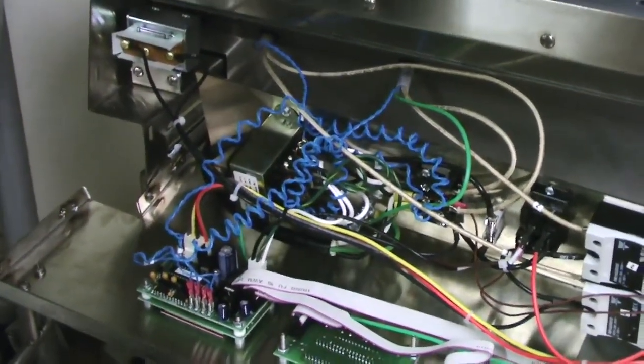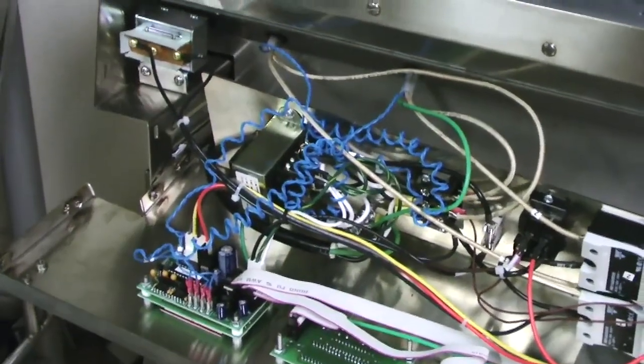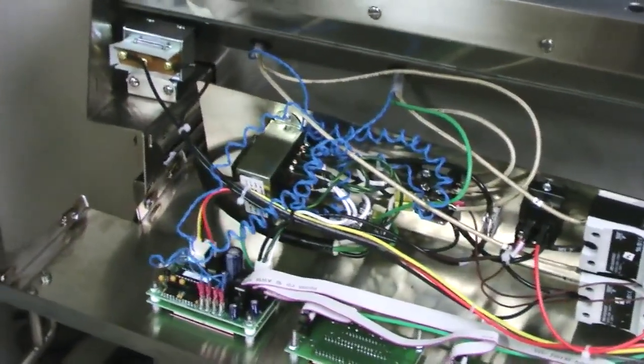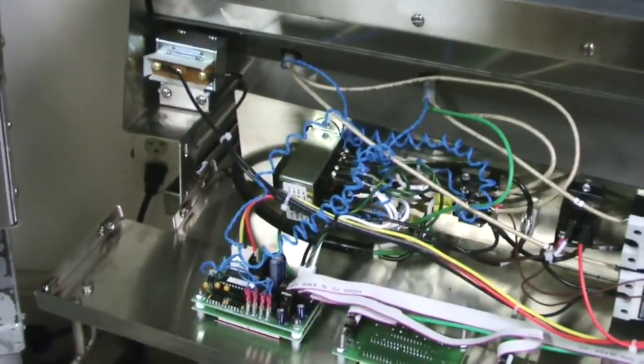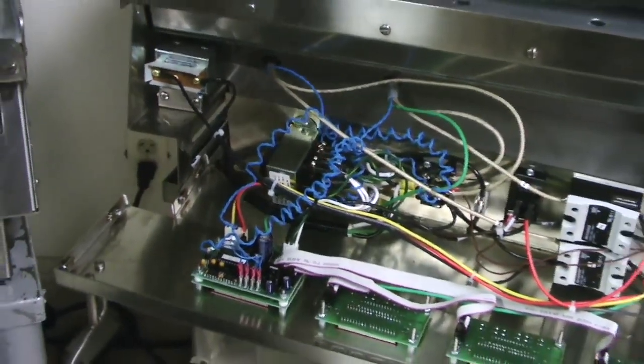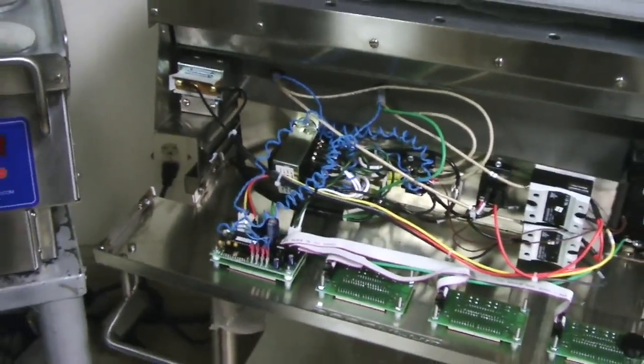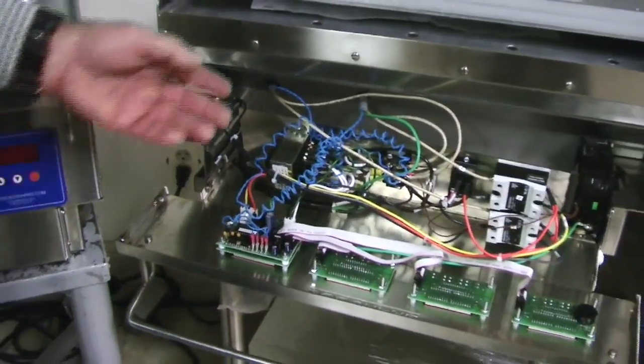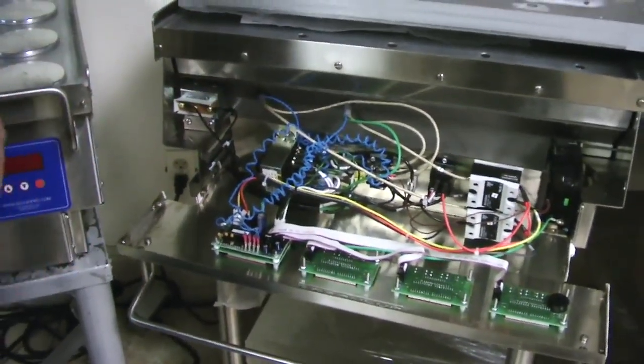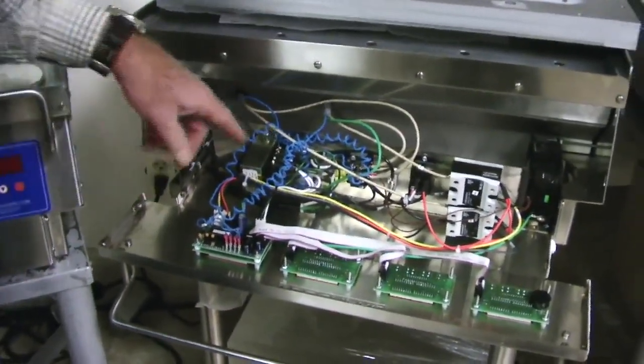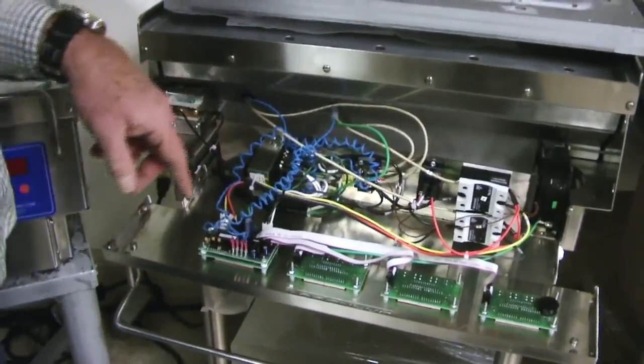If the transformer fails, a lot of it has to do with incoming spikes that come in from the store level, motors in the kitchen, or something that may have caused that transformer to go. It just needs to be disconnected and replaced. And you'll find out that's a problem if you're not getting 12 volts on the secondary side.